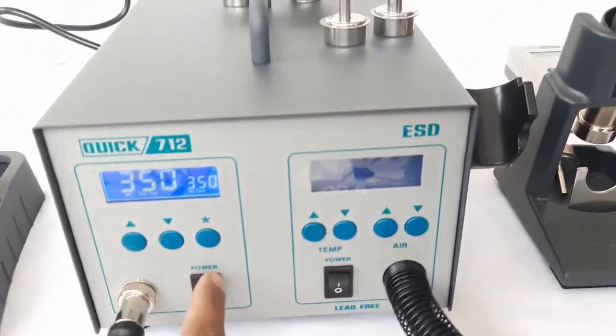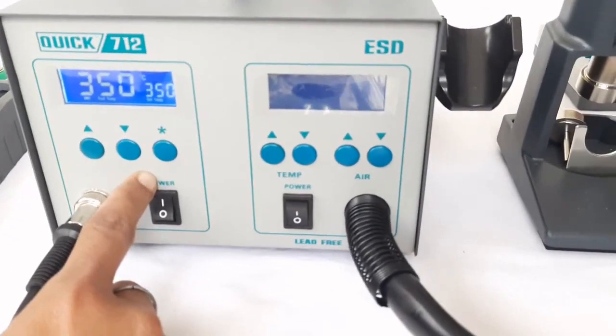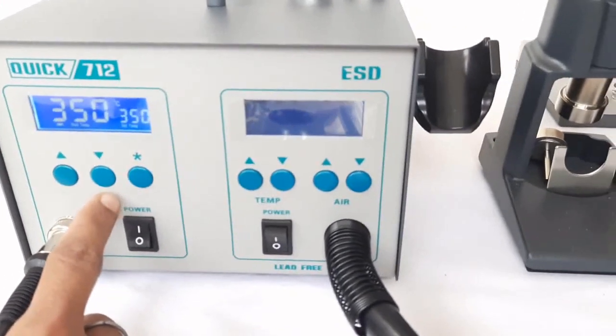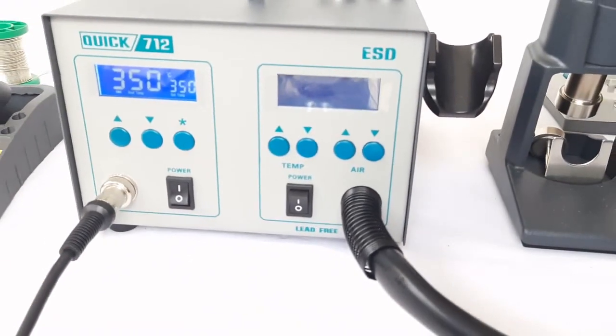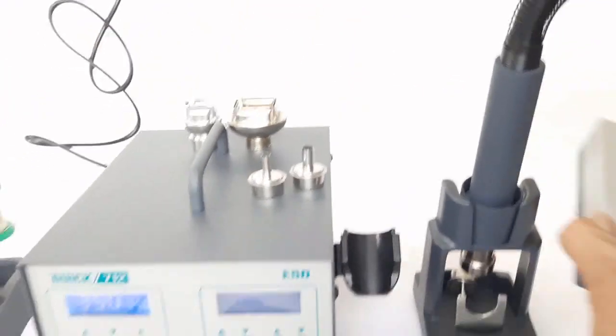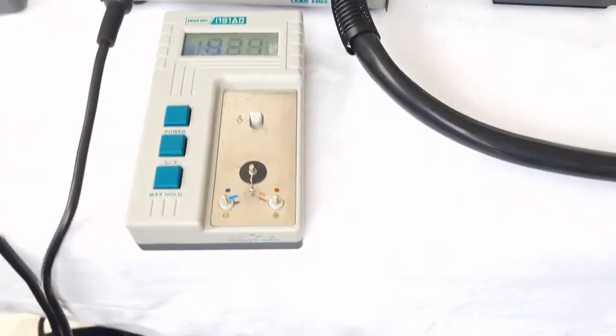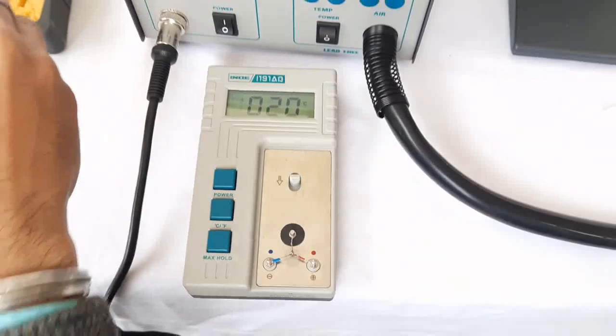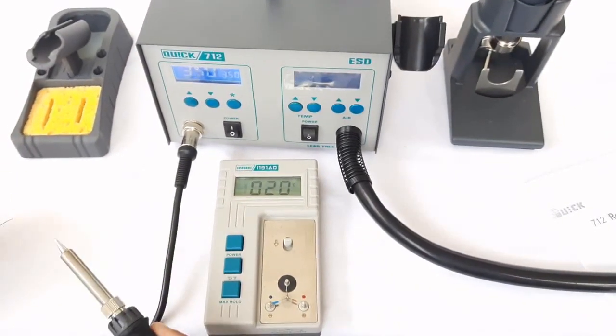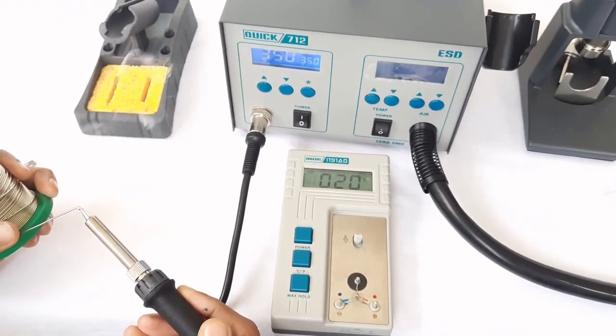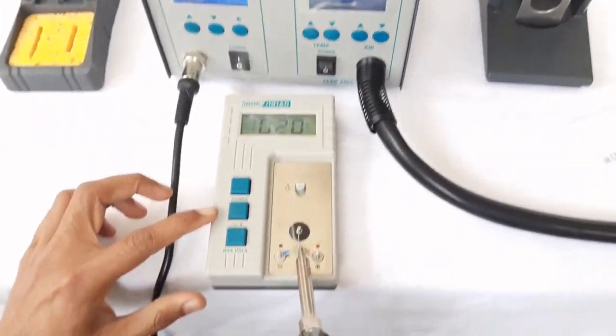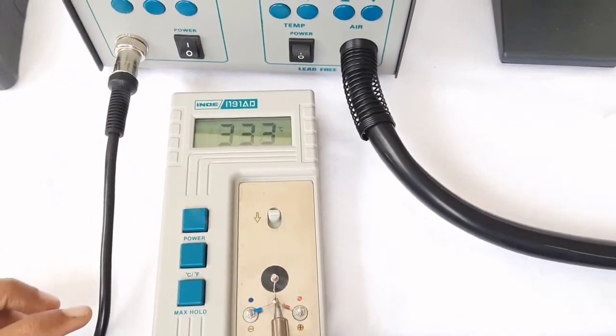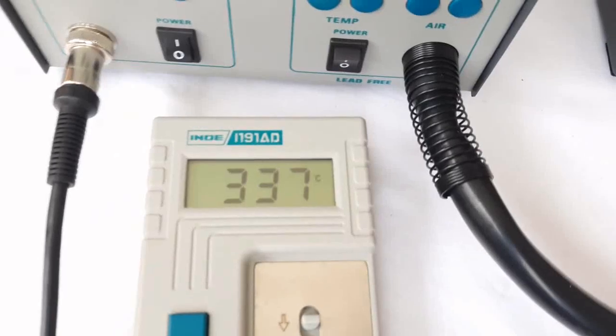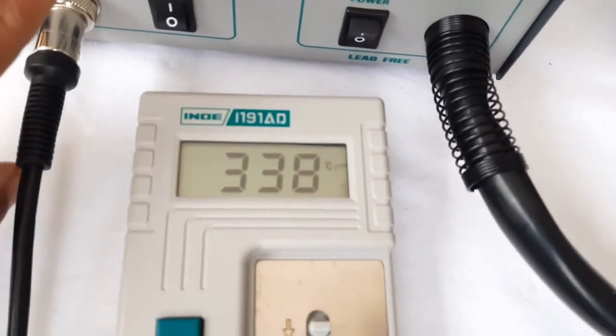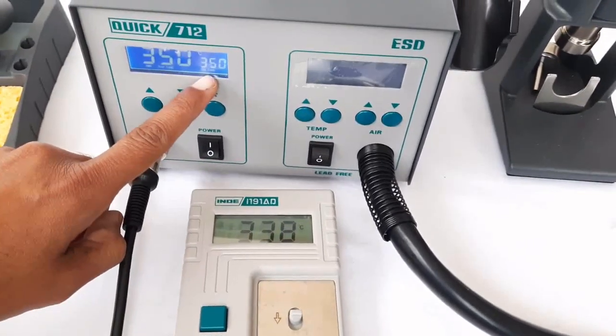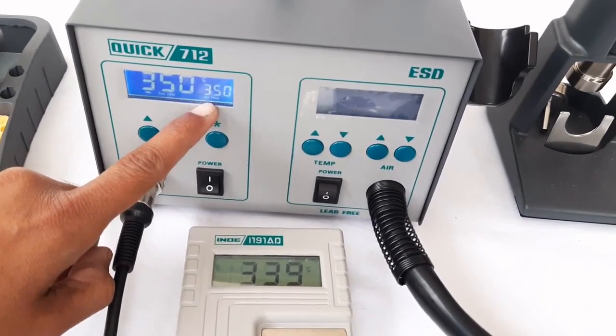Now we'll move to next step, and we will show you how to calibrate this unit. Calibration is often required to maintain the quality standards. For calibration, we need to measure the tip temperature with the help of this external calibrator. We will use fresh solder. We will wet it with fresh solder and check the actual tip temperature, which is close to 340. However, the set temperature is 350, so there is a variation on the downside around 10 degrees centigrade.